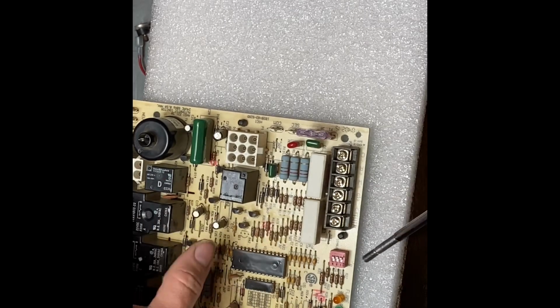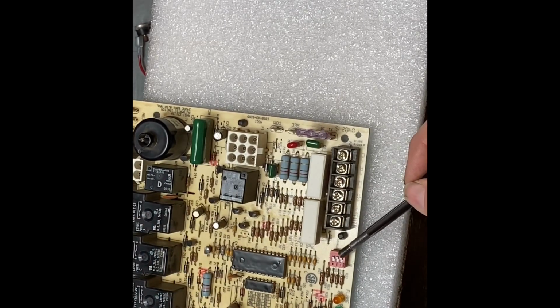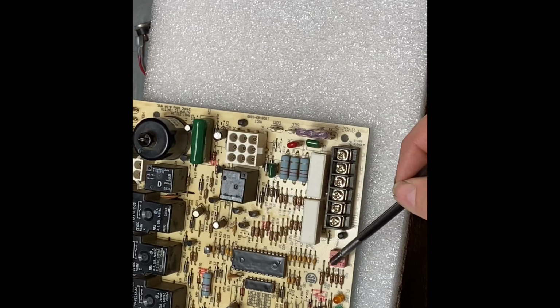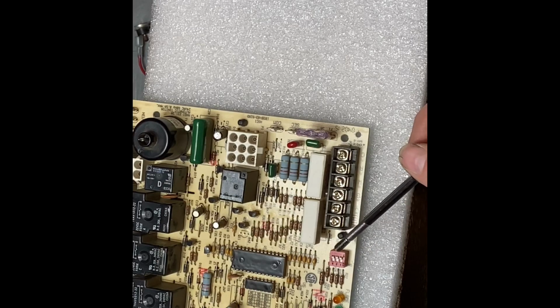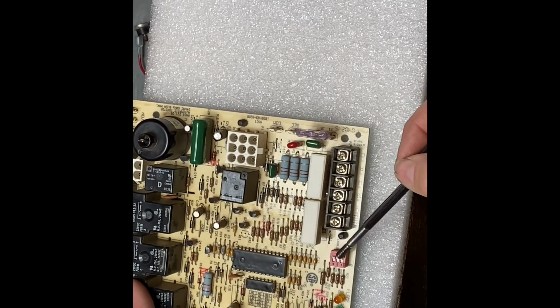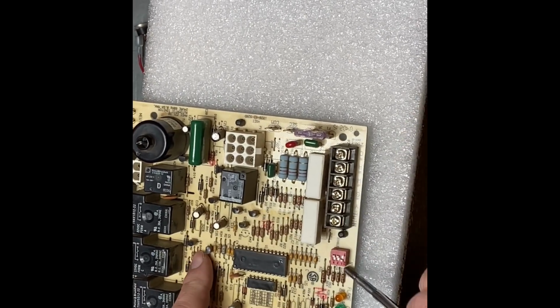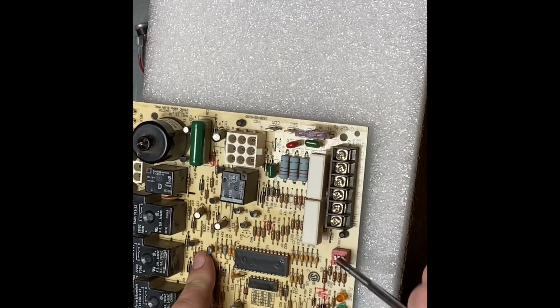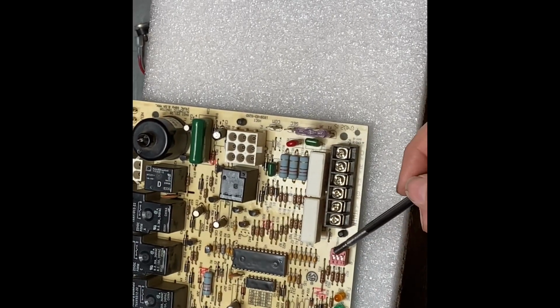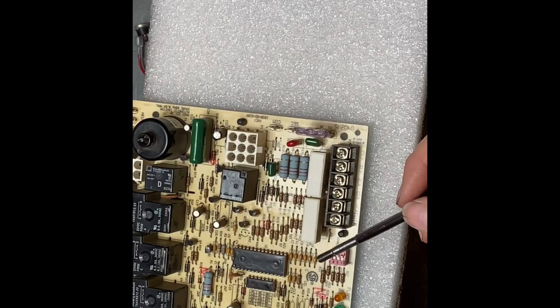Next thing I want to point out on this is these little dip switches. This is where you're going to have to RTFM, read the fabulous manual. We use these dip switches in different combinations to adjust the fan off delay or many other options for this control board. To move these dip switches, dual in-line package, you just simply push them back or forth, and the control board and the wiring diagram is going to give you a specific reason for how you want to set these up.